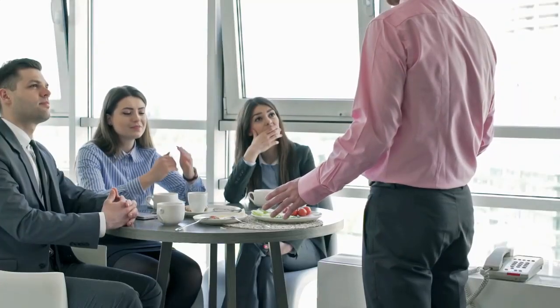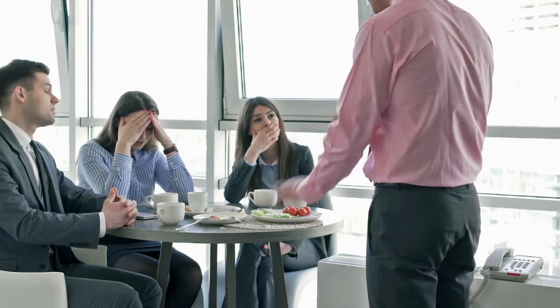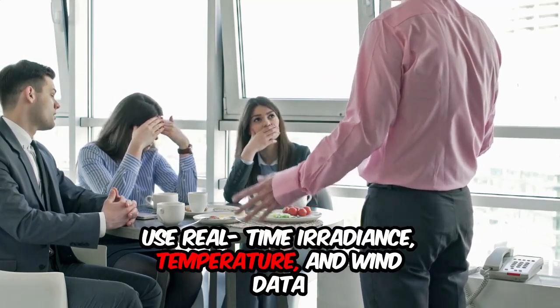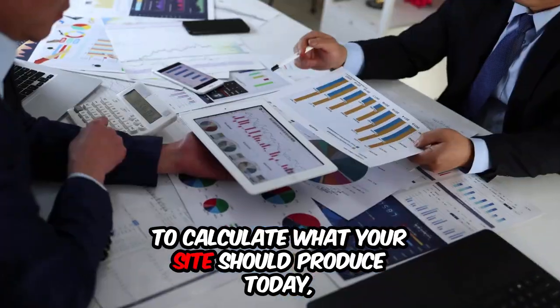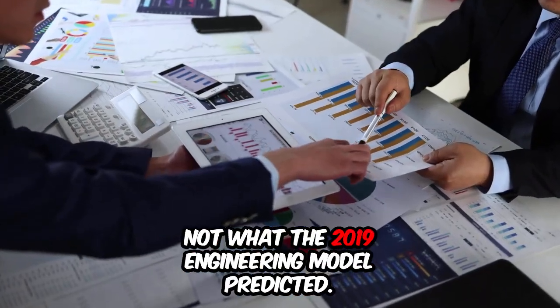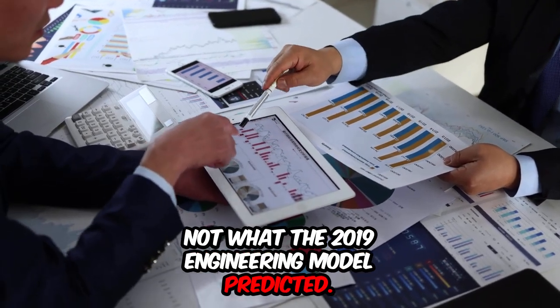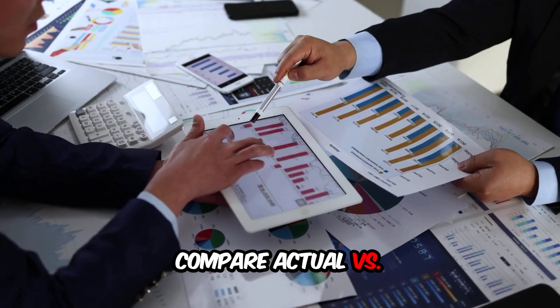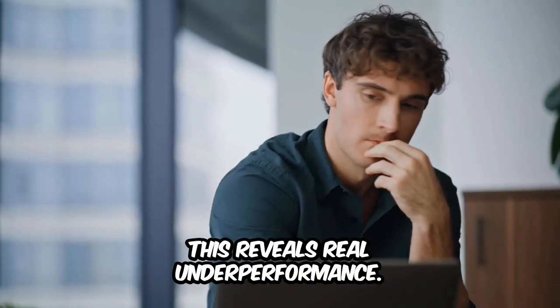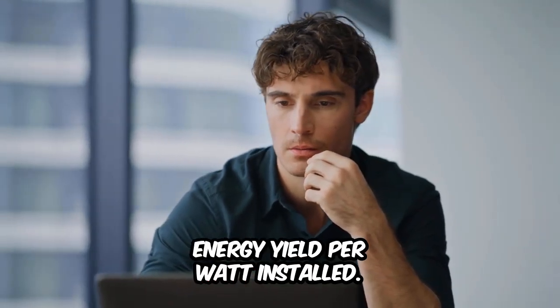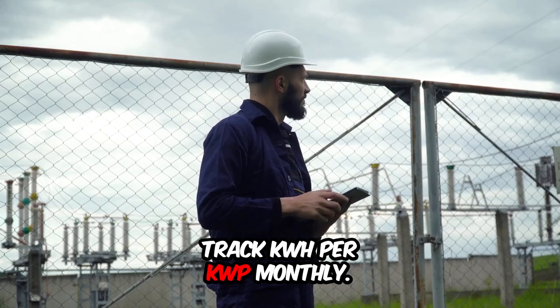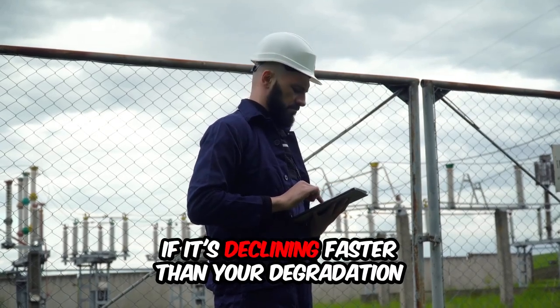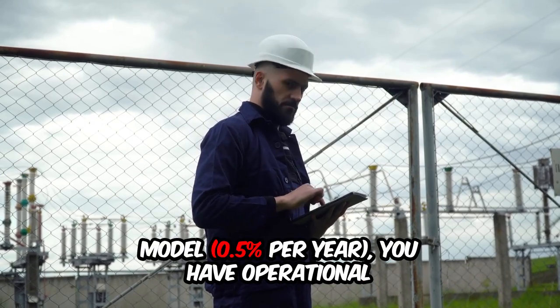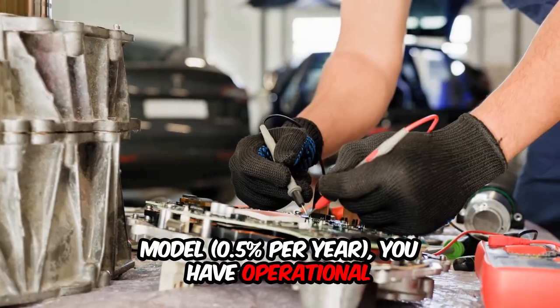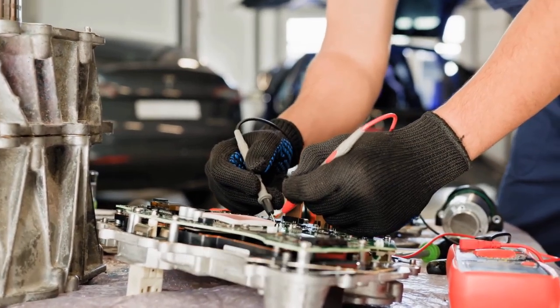Metric number 2, weather-adjusted production. Use real-time irradiance, temperature, and wind data to calculate what your site should produce today, not what the 2019 engineering model predicted. Compare actual versus weather-adjusted expected. This reveals real underperformance. Metric number 3, energy yield per watt installed. Track kWh per kWp monthly. If it's declining faster than your degradation model, so 0.5% per year, you have operational issues, not just aging equipment.